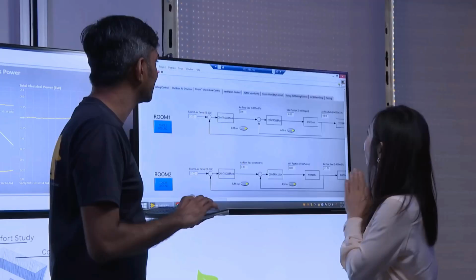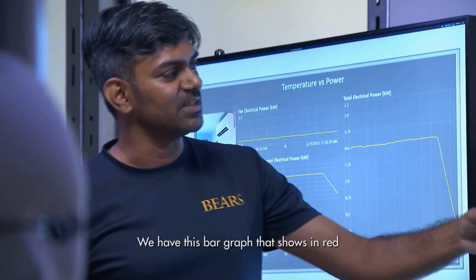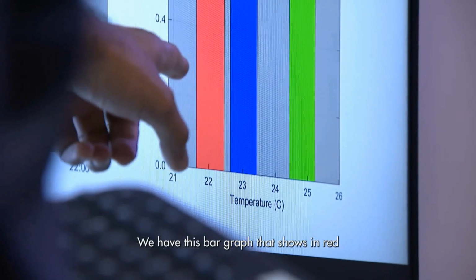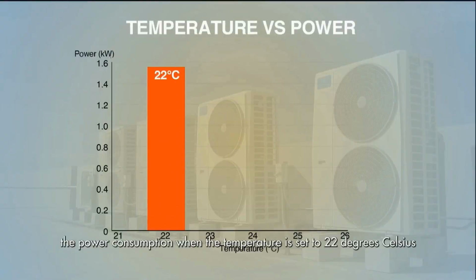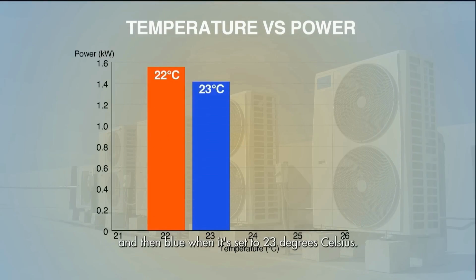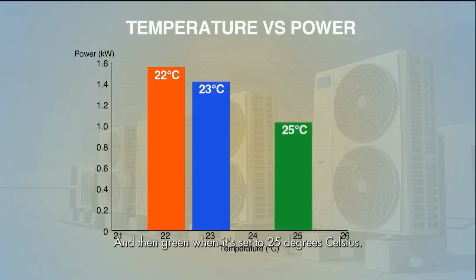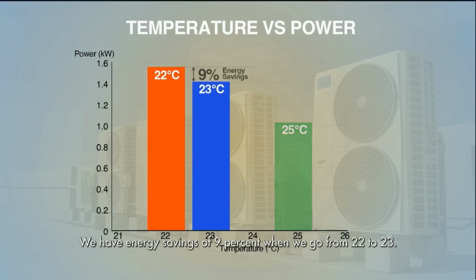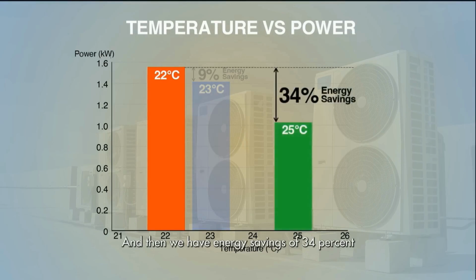The results are in, I'm excited. We have this bar graph showing in red the power consumption at 22 degrees Celsius, blue at 23, and green at 25. We have 9% energy savings going from 22 to 23, and 34% energy savings going from 22 to 25. That to me is quite substantial, especially from a household expenses point of view.